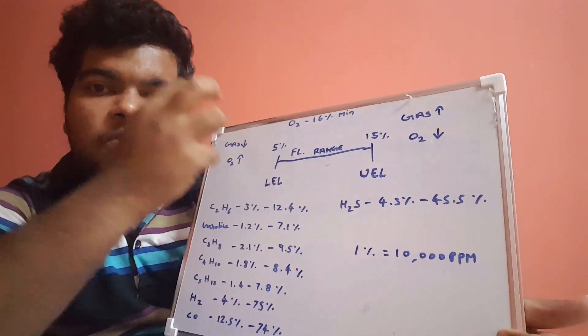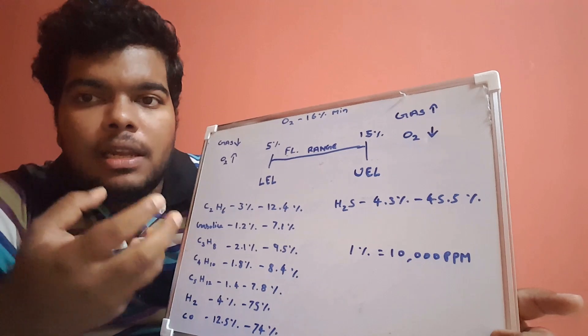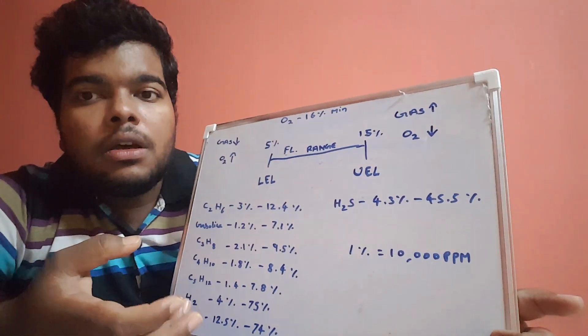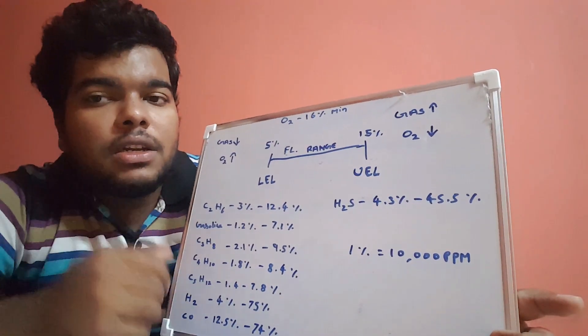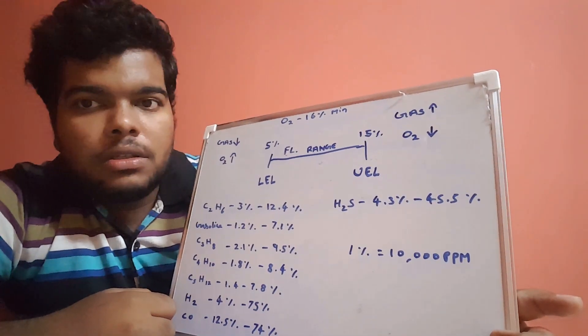We know that 1 percentage is equal to 10,000 ppm. So if 5 percentage of LEL is available in air, then it has the capacity to ignite when there is sufficient oxygen in place and in the presence of a heat source as well.